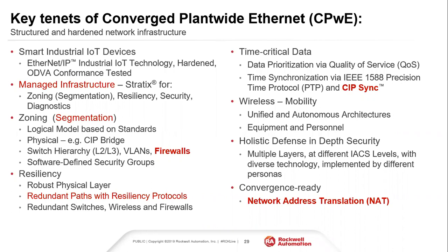And how do you want to do that tying in from third party to non-third party equipment? So one of the big benefits that Rockwell has, when we're looking at the ControlLogix, all those Ethernet adapters that I was talking about, we do what's called CIP bridging. So via the backplane, I can go in one Ethernet adapter, go via the backplane and go out the other Ethernet adapter. If you guys have ever done ControlNet, DeviceNet, you've done this all the time. If you've used our RSLinx or any of those, you know that you can go through Studio 5000, connect via one adapter, and then see all of the IO underneath. That's essentially what we're doing there.